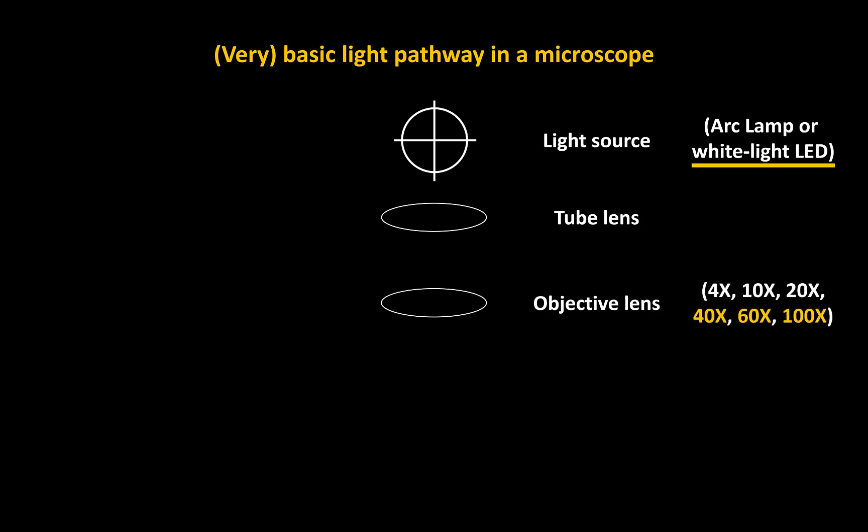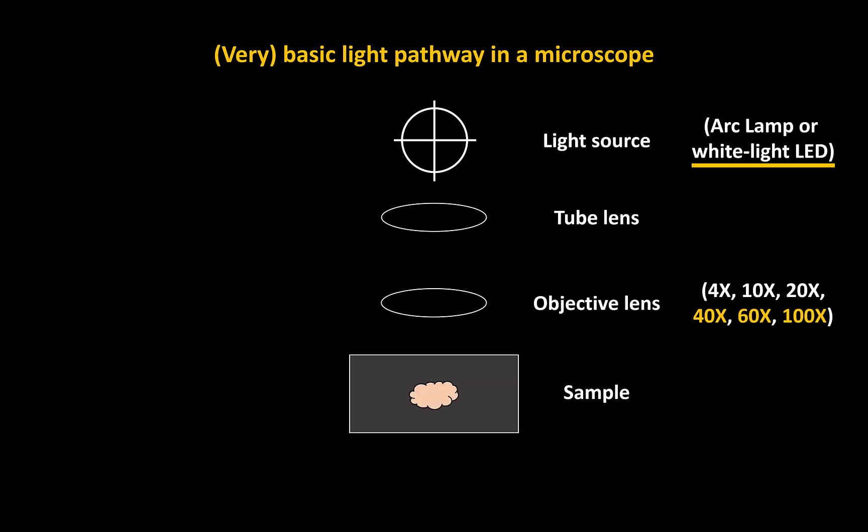There's a 4x, a 10x, and a 20x, all of which are air-based objectives. And then we have a 40x, a 60x, and a 100x as well. The 40 through 100x are all oil-based objectives. The light source goes through these lenses and eventually is able to excite our sample.